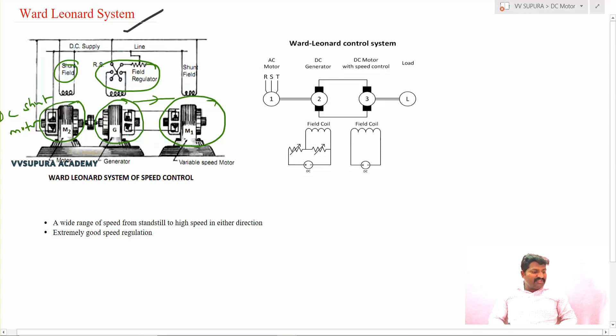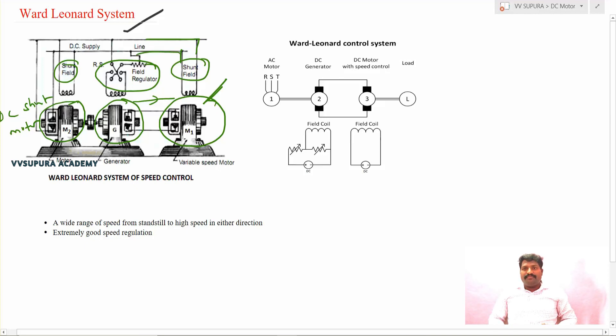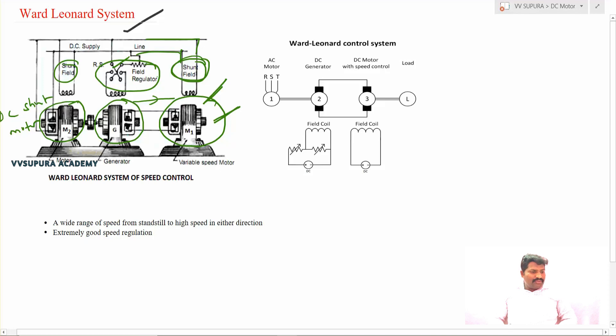By using field regulators, I can control the output of the generator. The output of the generator — the generated EMF — is variable in nature, and this variable voltage is given to the motor whose speed is to be controlled. The field supply of that motor is kept constant by directly connecting it to a DC supply. So the electrical energy supplied to the motor through the generator is varied using the field regulators while maintaining constant field supply.